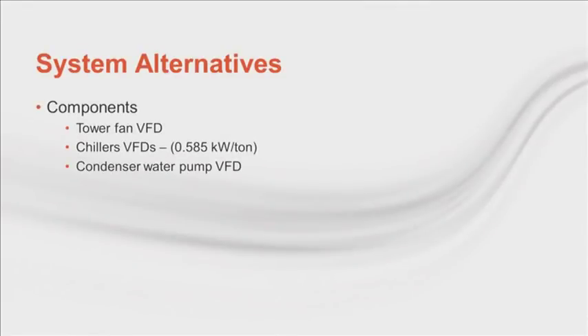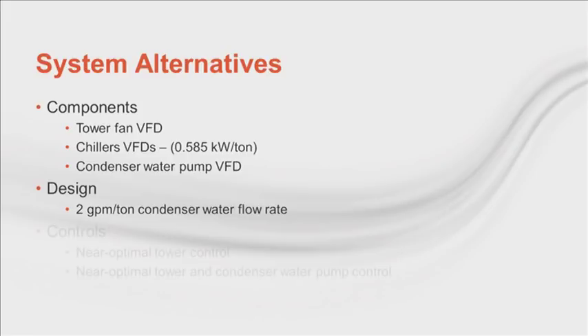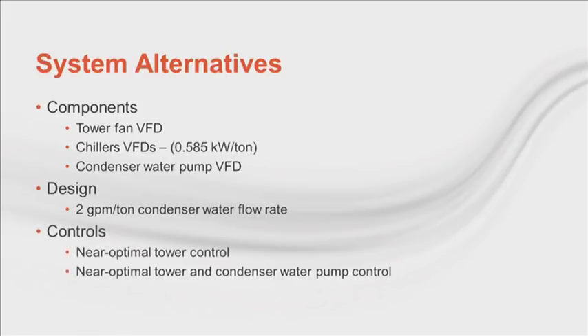There are many variations in the system to consider when discussing optimizing the water-cooled condensing system. Each component could have a variable speed drive. Based on our earlier trends, code requirements, and practicality, I'm going to assume that all components have drives on them. This leaves us with design and control options for the condenser system. Now, the original designer gets to pick the condenser water flow rate. What if it were lower, say 2 GPM per ton? This probably means a different chiller selection if the chiller is centrifugal, and the designer and the controls company must work together to optimize the sequence. That's true whether it's just tower set point optimization or a combination of condenser water pump and tower controls.